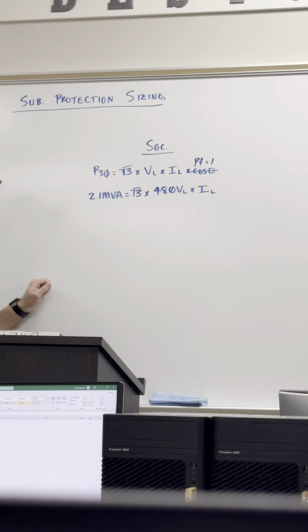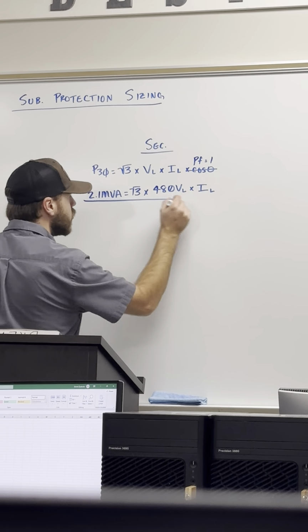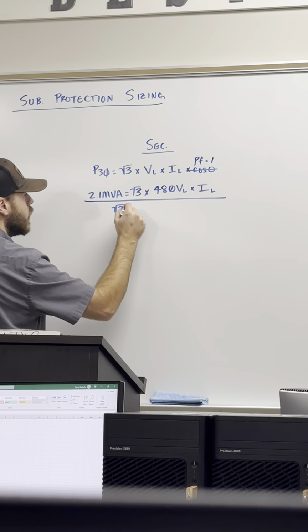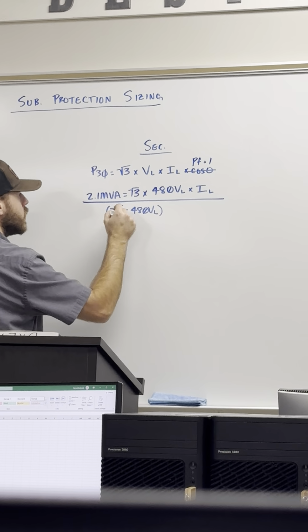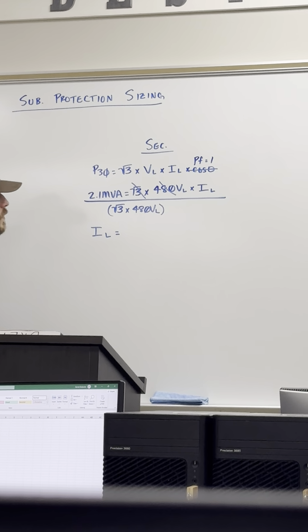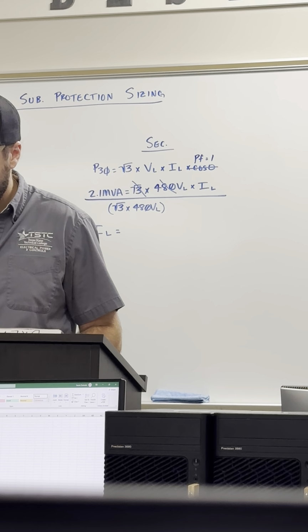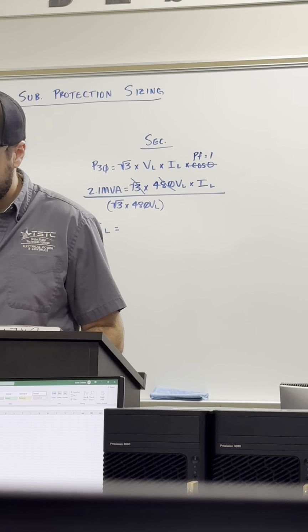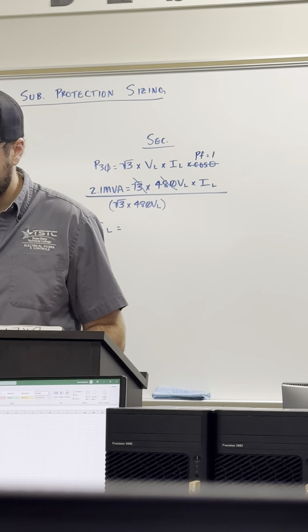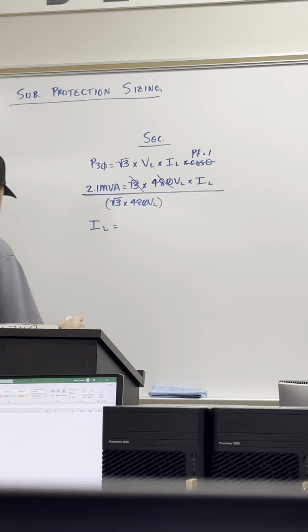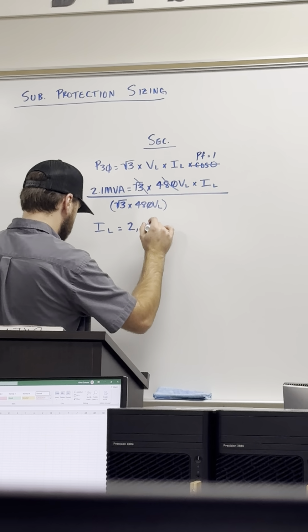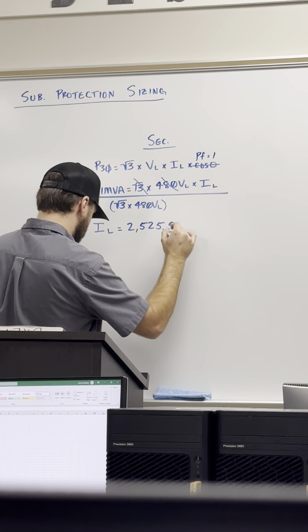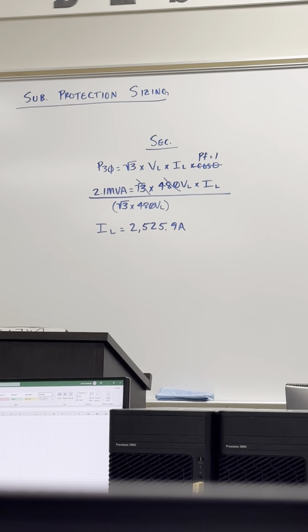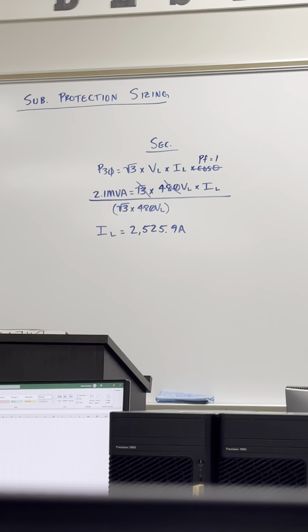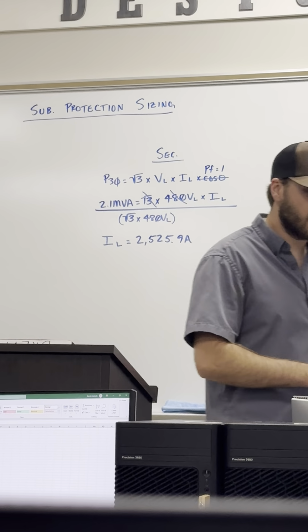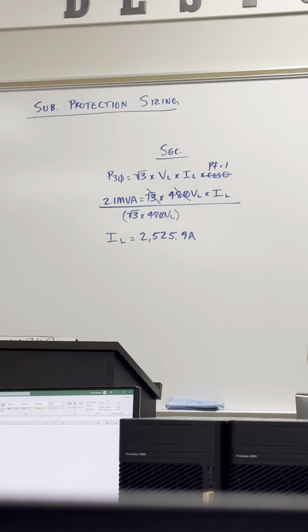But now I'm solving for current. So, solving for current, we're going to take both sides, divide it by square root of 3 times 480 volts. Don't forget parentheses when you do that. And when I calculate that, I get 2,525.9 amps. So it is slightly higher than what we summed up, which makes sense. So that is our transformer rated current.